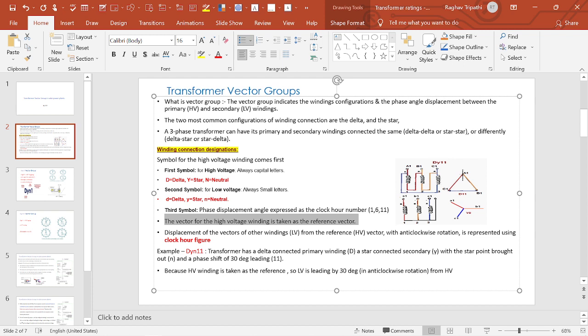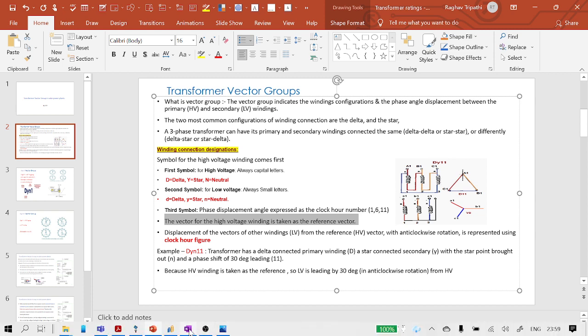In DYN11, HV is delta, LV is star with neutral, and 11 stands for the phase angle displacement — meaning the LV winding is leading 30 degrees from HV in anti-clockwise rotation. The HV winding is the reference, so LV is leading by 30 degrees in anti-clockwise rotation from the HV.